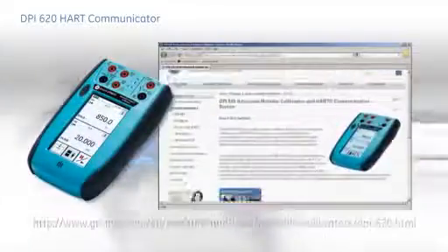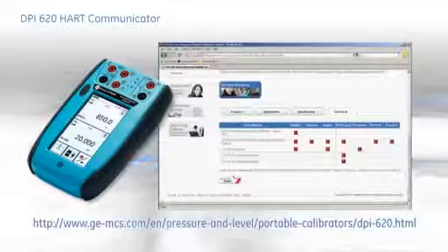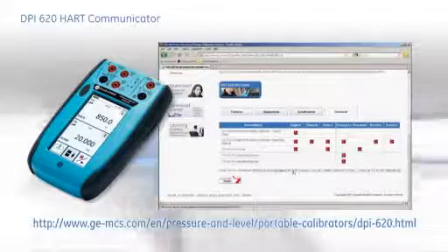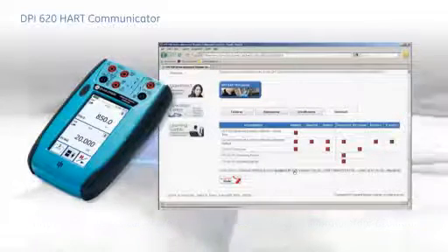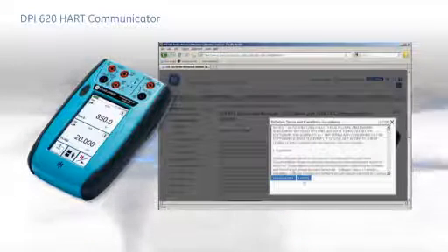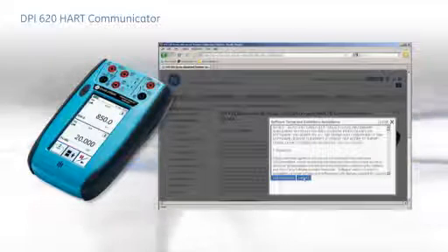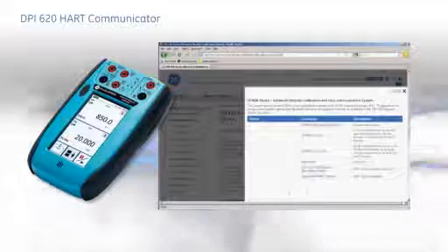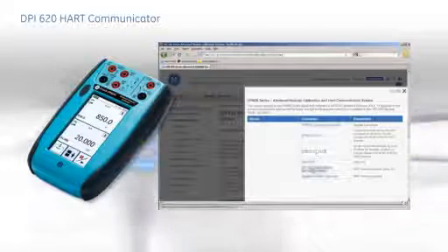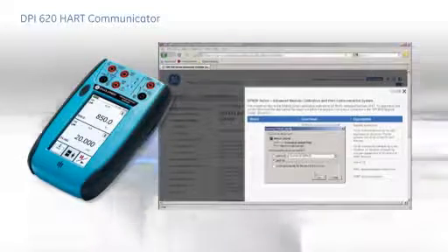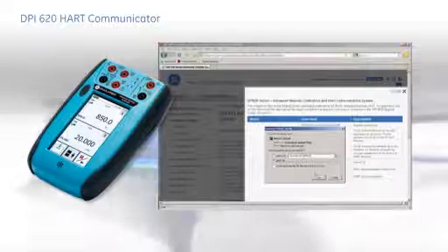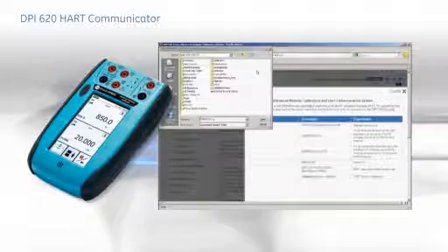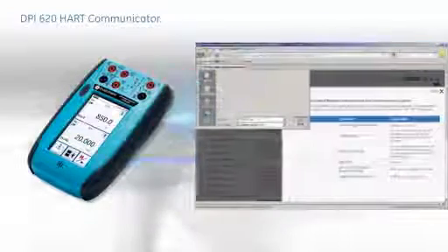The DPI-620 is the ideal communicator for configuring and calibrating HART protocol devices. A full library of HART registered device descriptions, DDs, is stored on board. That's over a thousand devices. New DDs can be added by free internet download, which means no ongoing support and registration fees.